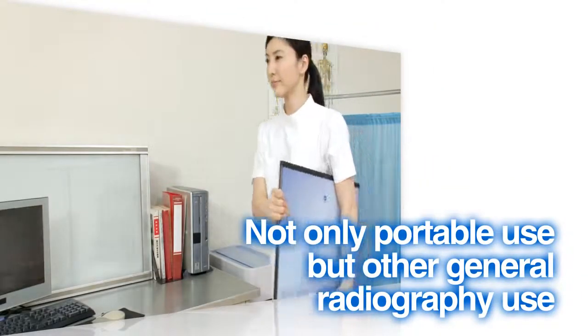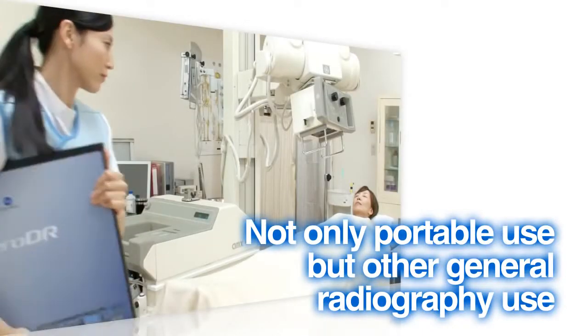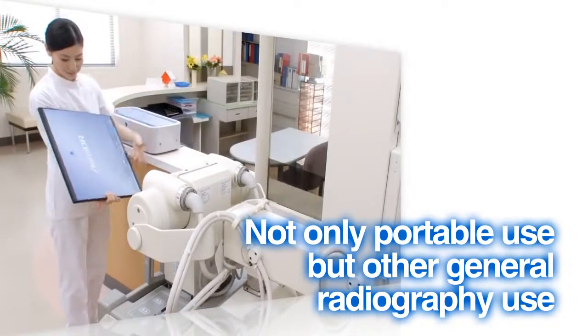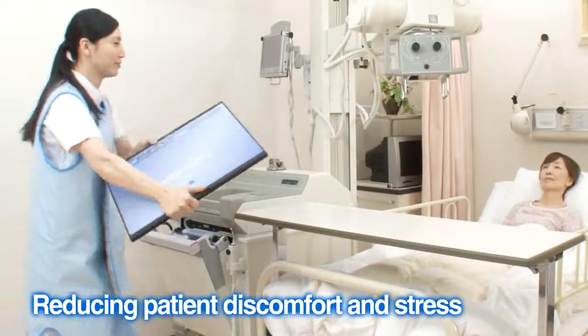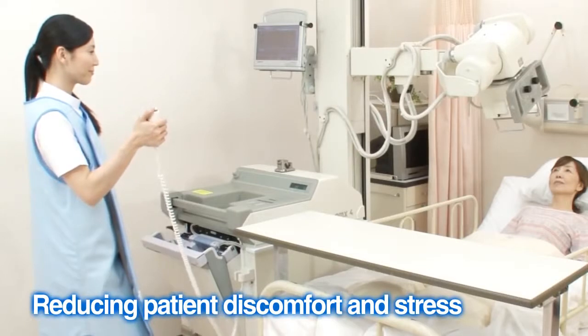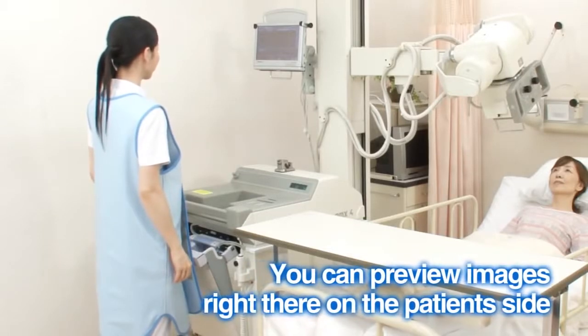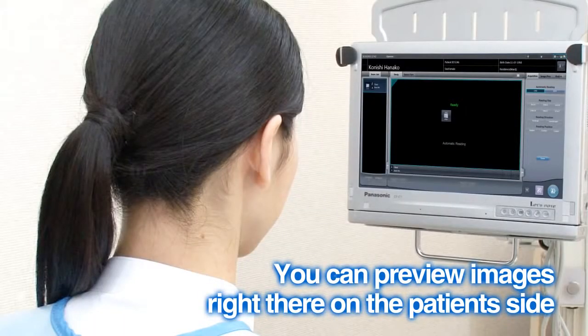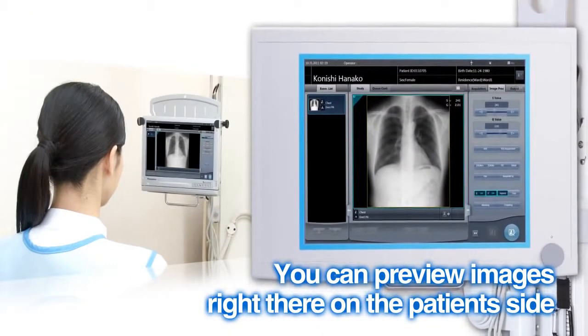The shared FPD solution with roaming technology permits an AeroDR panel to be used interchangeably in general radiology departments and in the emergency and surgery rooms, as well as for the portable x-ray system. The lightweight and cable-free operation of the AeroDR wireless digital flat panel detector system allows for easy patient and image detector positioning, while reducing patient discomfort and stress during portable procedures. The AeroDR portable imaging console can deliver an image preview in approximately 3 seconds, allowing review of the x-ray image to determine if re-exposure is needed prior to leaving the patient's side.